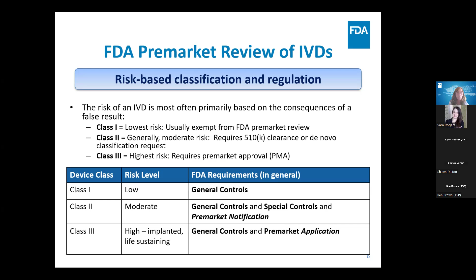manufacturing practices. And then class 2 and class 3 devices are also subject to these general controls, but class 2 moderate risk devices are also subject to special controls, which are specific requirements for specific device types. And then a pre-market notification submission requirement, or a 510K, where FDA would review data and protocols before a device is marketed.